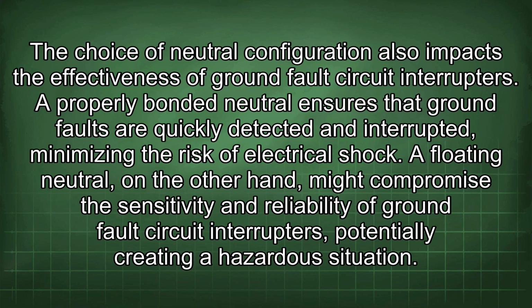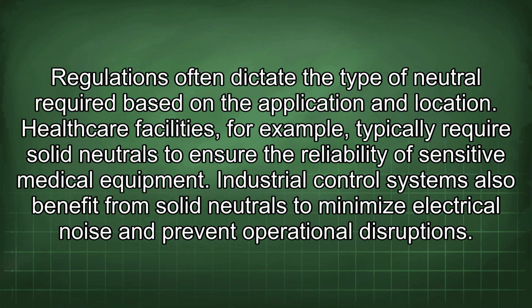The choice of neutral configuration also impacts the effectiveness of ground fault circuit interrupters. A properly bonded neutral ensures that ground faults are quickly detected and interrupted, minimizing the risk of electrical shock. A floating neutral, on the other hand, might compromise the sensitivity and reliability of ground fault circuit interrupters, potentially creating a hazardous situation. Regulations often dictate the type of neutral required based on the application and location.